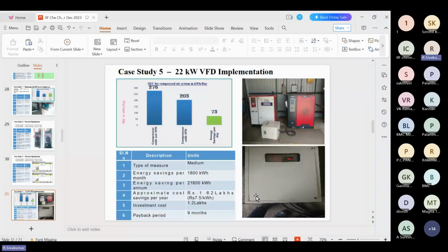One more unit has 2 compressors, and only 1 compressor is running at a time. So we suggested implementing one common VFD for both compressors. The unit saved around 73 units per day, because this unit is also running for 16 to 18 hours in a day. So in a year, they saved 21,600 units. Cost saving is 1.62 lakhs. The investment cost is 1.2 lakhs. The payback period is 9 months.